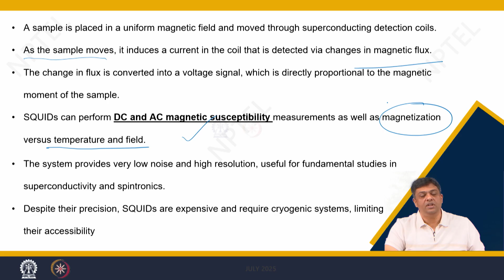You can have both modes, DC as well as AC magnetic susceptibility measurements. And now suppose you perform the measurement at 4K, you can perform the measurement at 10K, 20K, and hence you can carry out the measurements as a function of temperature or varying fields. So, you can determine the magnetization. Because of the use of such superconducting detection coils, you have very low noise, high resolution, making this a versatile technique for carrying out fundamental studies in superconductivity and spintronics. Yes, SQUIDs are expensive, which can sometimes limit their accessibility, but if you look around now in India, nearly all central universities, major institutes, and many of the privately funded institutes where research is also being carried out, they have SQUID. So, it is no more that their accessibility is limited, but you have to talk to people and get access to this measurement, and you can determine the properties of the nanomaterial which you have synthesized.